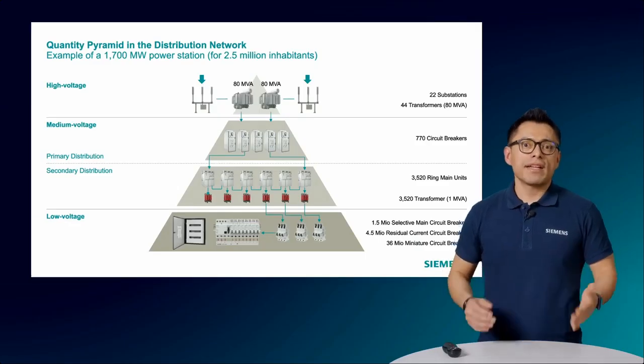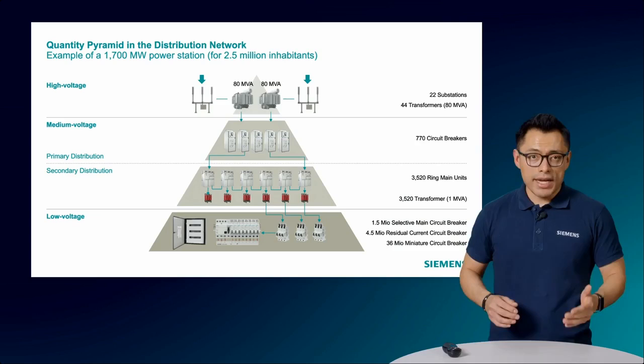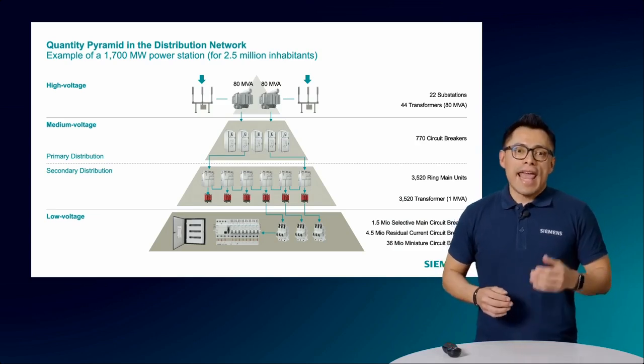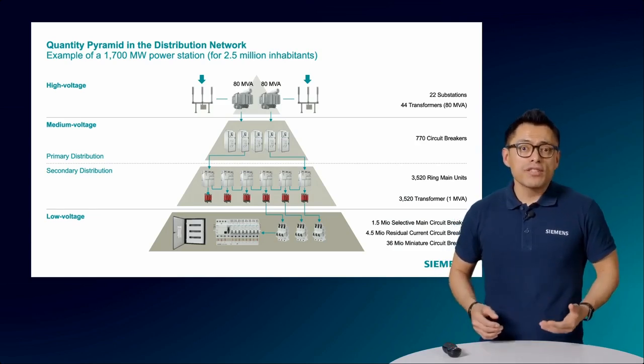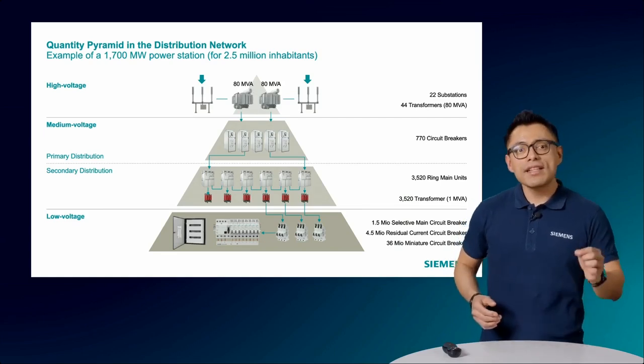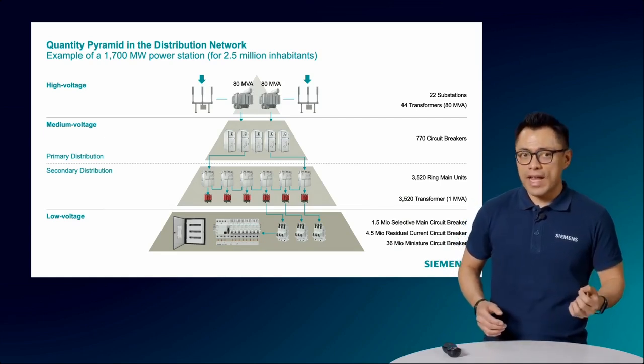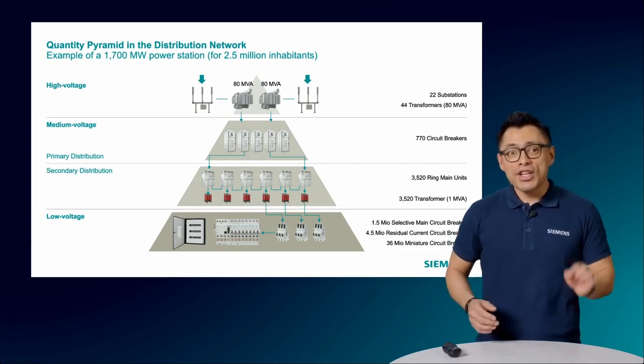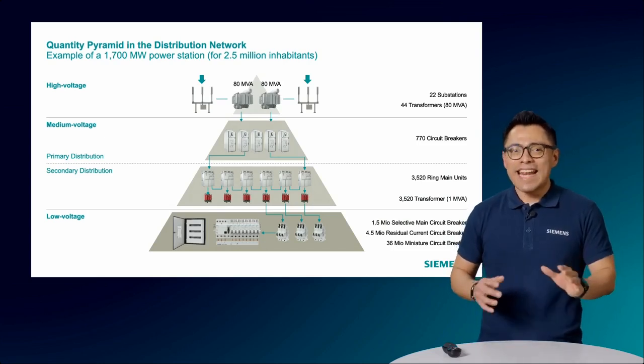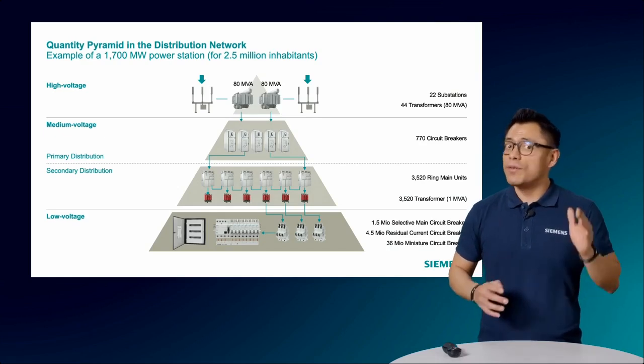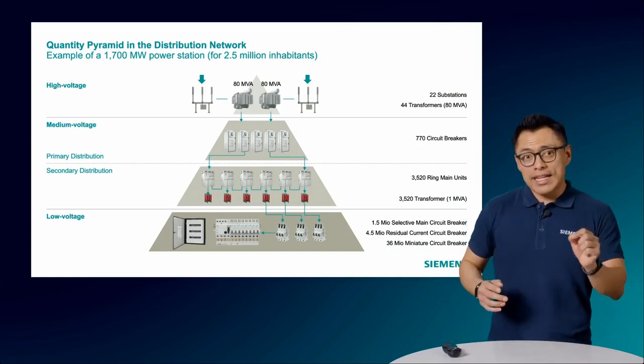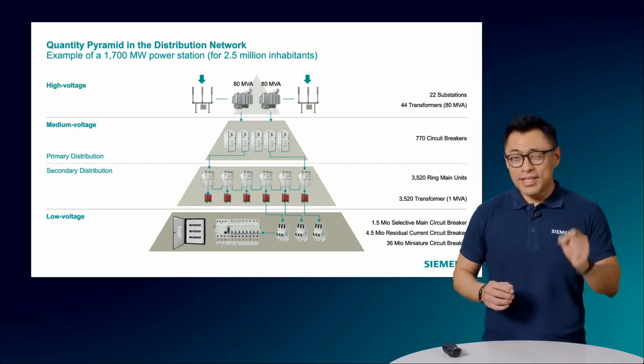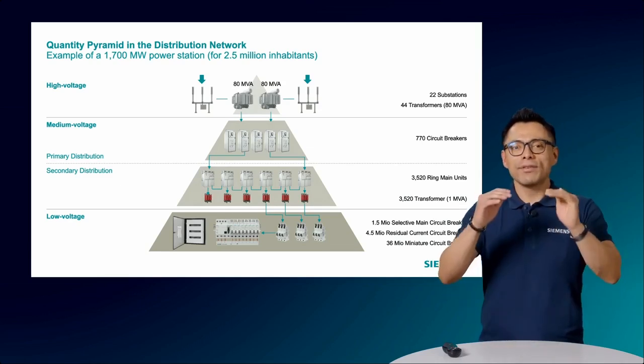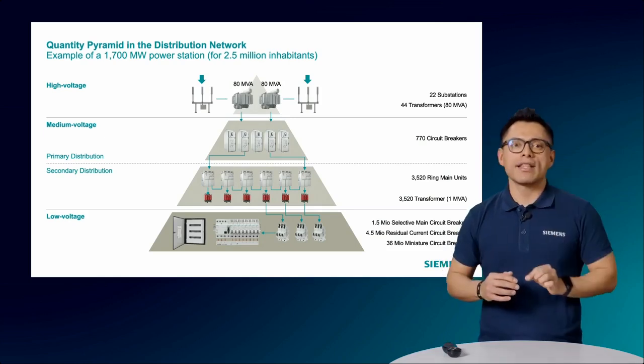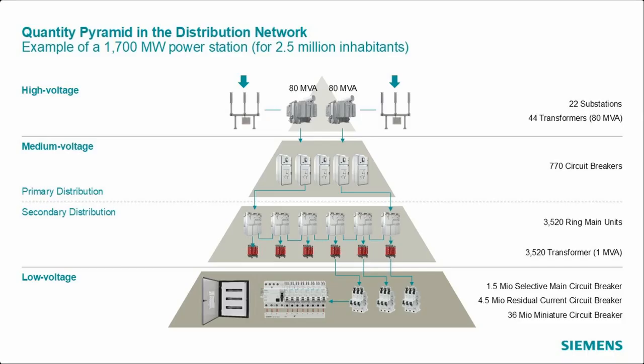Then comes the final stage at the bottom of the pyramid, meaning low voltage. And here is where the quantity of components really starts to increase. It basically depends on the number of consumers. I will not go into more details, just observe please that the quantities are enormous compared with the first 44 transformers, for example. But important here is to ask you, did you notice the rule? The higher the voltage level, the fewer the components, and vice versa. The lower the voltage level, the more components.